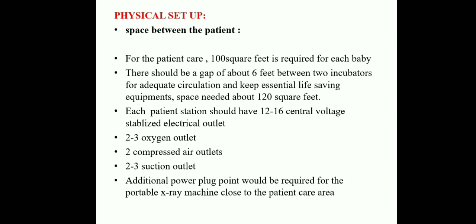Okay, and next, each patient station should have 12 to 16 central voltage stabilizer electronic outlets for the physical setup, and 2 to 3 oxygen outlets, 2 compressed air outlets, 2 to 3 suction outlets. In addition, a power plug point would be required for the portable X-ray machine close to the patient care area. Nowadays X-ray machines are portable and mobile, no? So extra plug points are also needed for maintaining that physical setup.